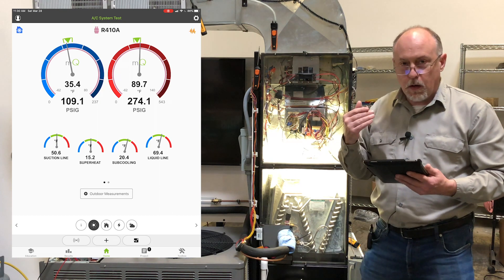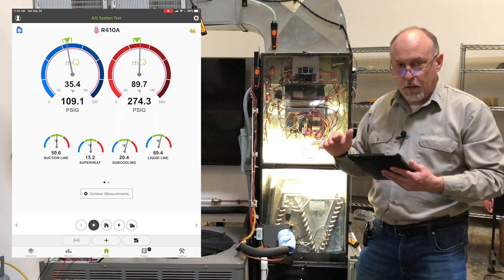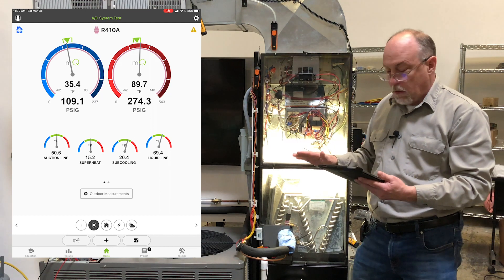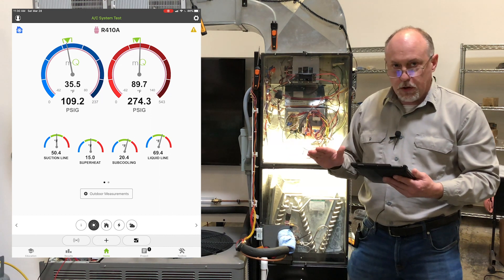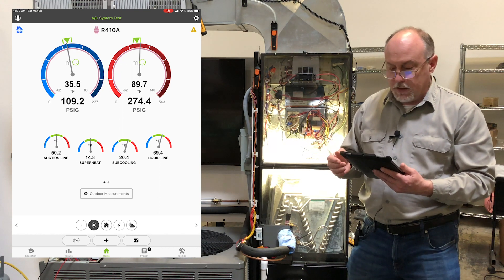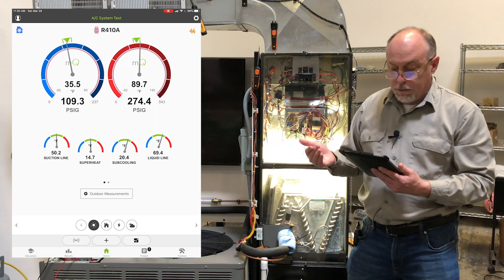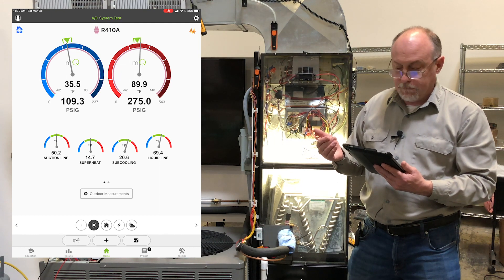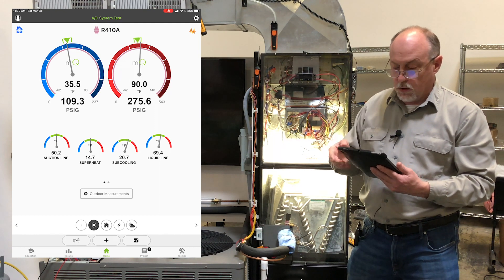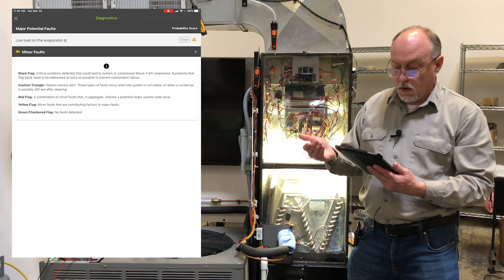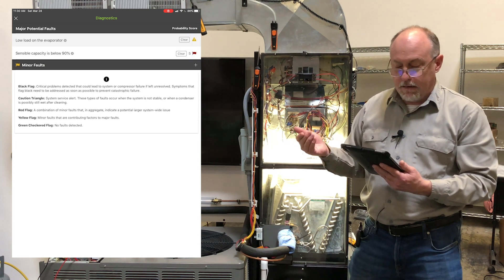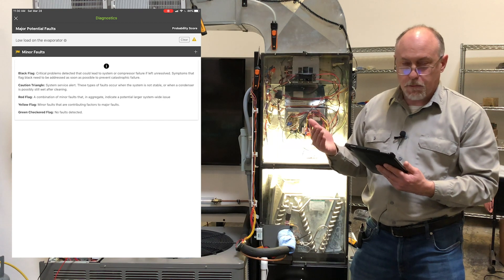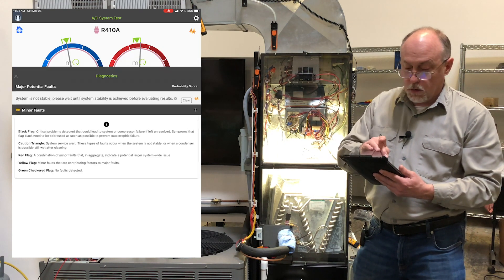And so what I want to do now is benchmark this system so that once I have it set up exactly the way I want it, every technician in the future coming out will use this benchmark to evaluate the system performance. You can see my high pressure target is right on a threshold there. If I go in here, you can see I have low load on the evaporator. And I'm bouncing in and out on a low sensible capacity, because we don't have much load in here to work with.